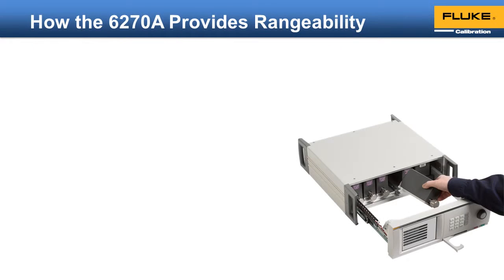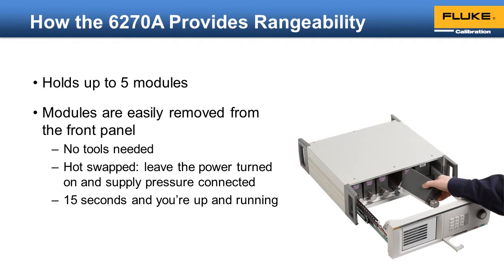How does the 6270A provide rangeability? First, you can install up to five measurement modules at any one time. These modules can be easily removed through the front panel — no pressure lines need to be disconnected from the unit and the power can remain on. So even if the 6270A is installed in a cabinet where you cannot get to the back of the unit, you can still easily switch out the modules.